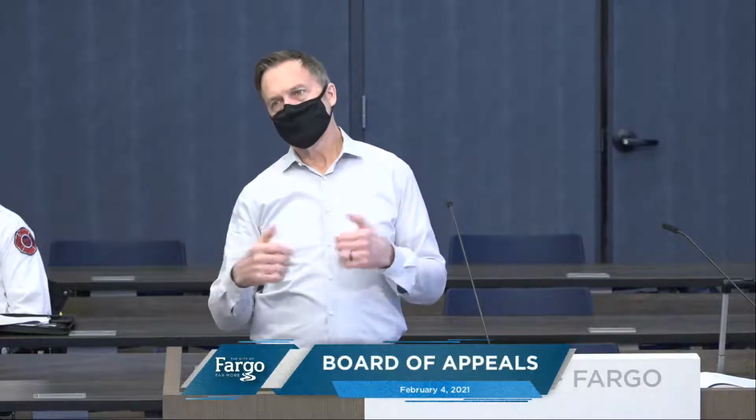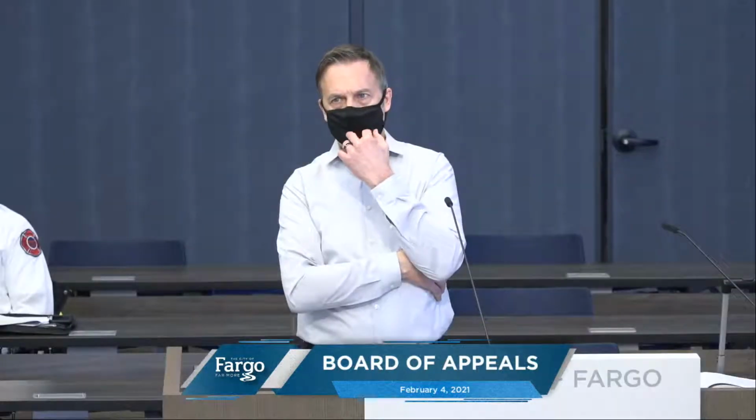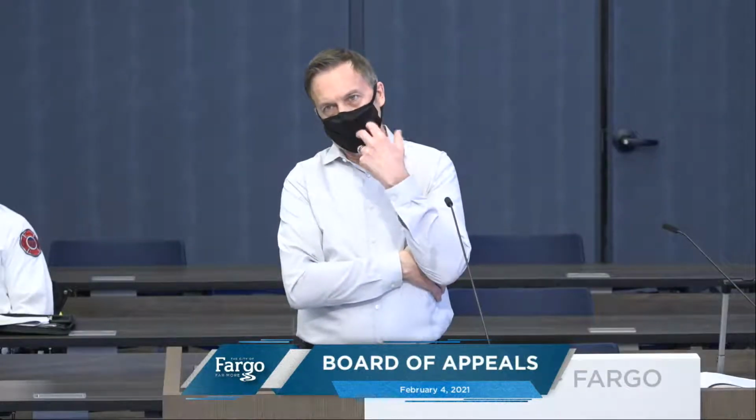That's kind of where I was going with my thought, that it's clear that the designer intended to have 1 hour separation between the garages because their code report says that. But the question here is where that 1 hour separation stops, and it looks like it's on 3 sides right now. It's on the sides between, and it's on the back wall, because you have a concrete wall there, on every wall except for the front. It'd be easy to do, yeah. But continuity is important.